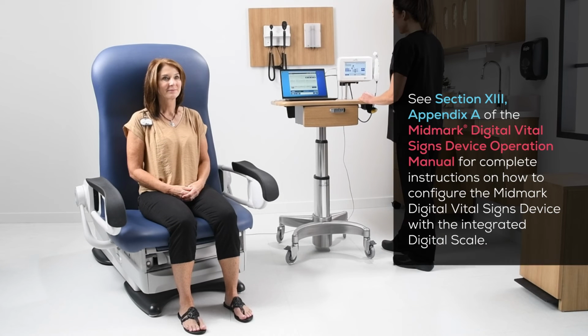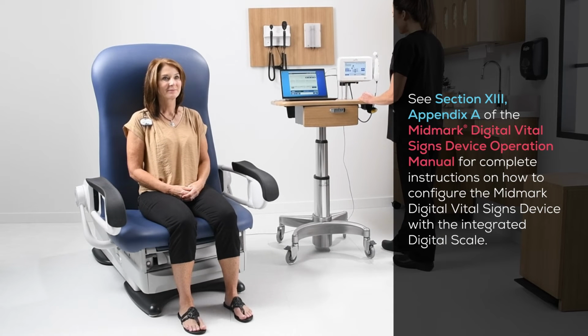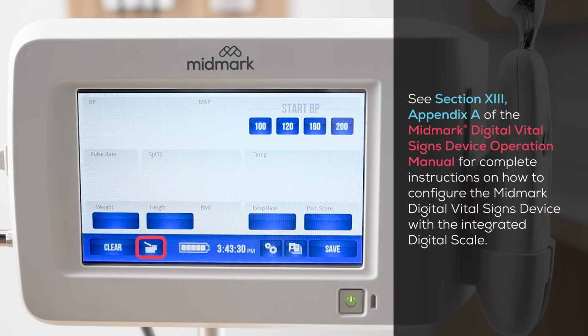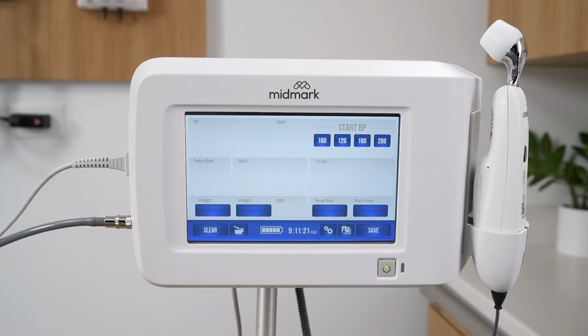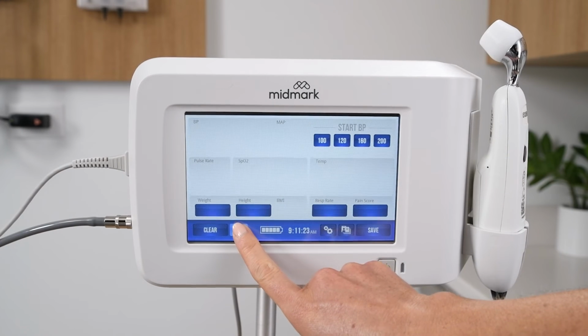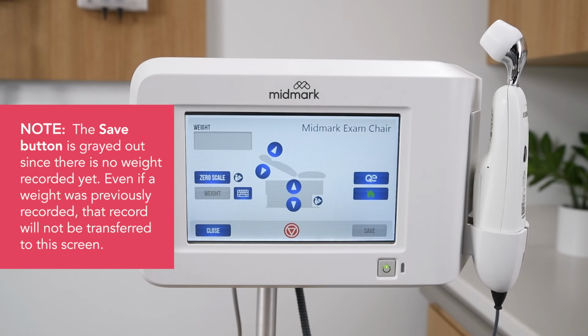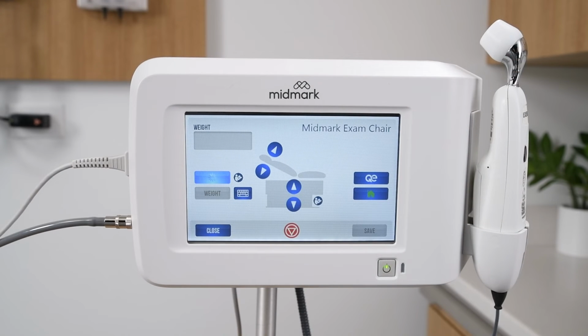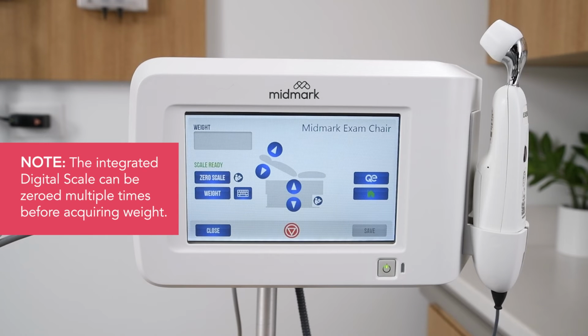When the Midmark digital vital signs device is configured with the integrated digital scale, the table scale icon button will appear to the right of the clear button on the Midmark digital vital signs device main testing screen. From the main testing screen, press either the weight button or the table scale button. The Midmark exam chair screen will appear. When the zero scale button is pressed, the button will display the in-progress wheel until the scale is zeroed. Once the scale is zeroed, a scale-ready message will appear and a weight button becomes active indicating the option to take a weight measurement is available.